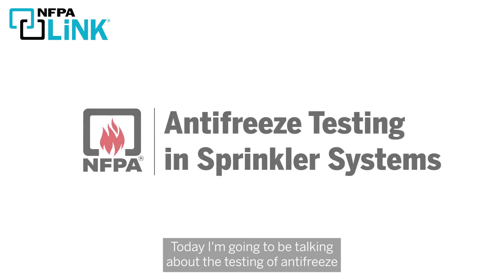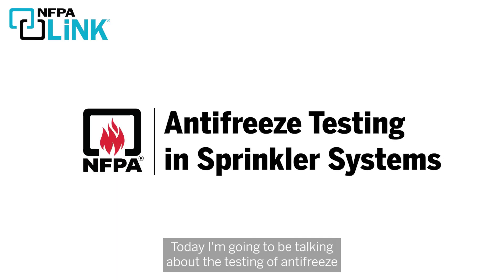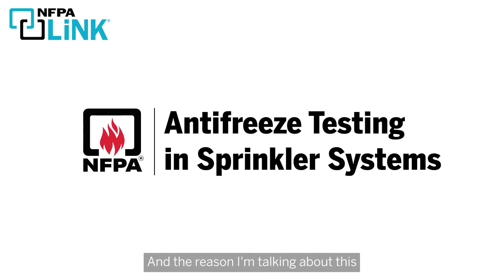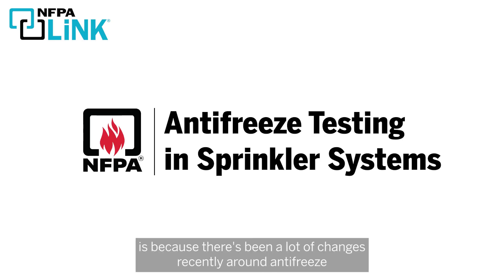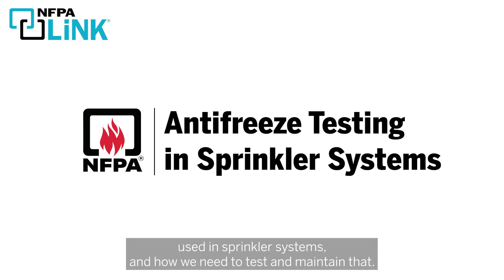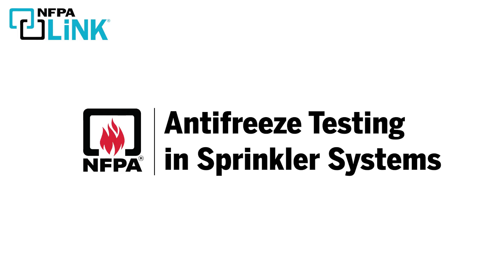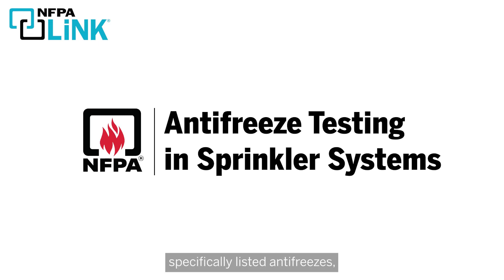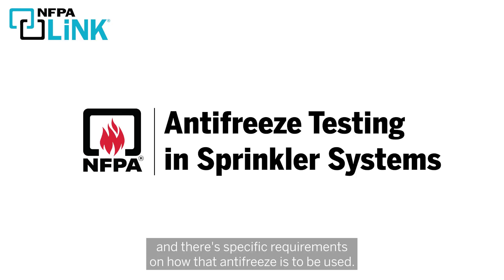Today, I'm going to be talking about the testing of antifreeze when I'm using it in a sprinkler system. The reason I'm talking about this is because there's been a lot of changes recently around antifreeze used in sprinkler systems and how we need to test and maintain that. The biggest change being that now we need to use specifically listed antifreezes and there's specific requirements on how that antifreeze is to be used.